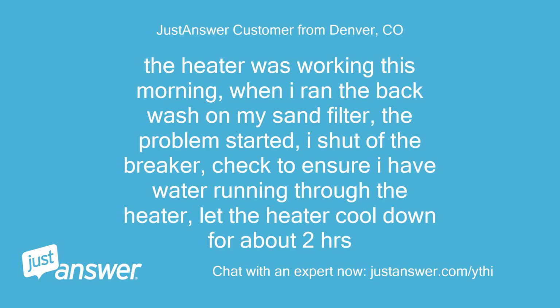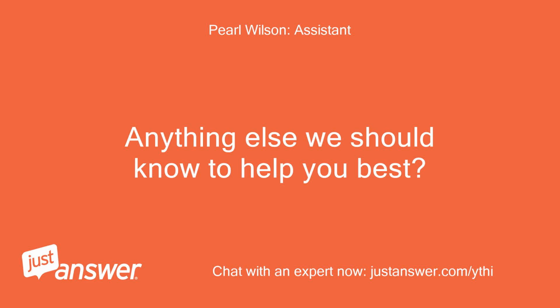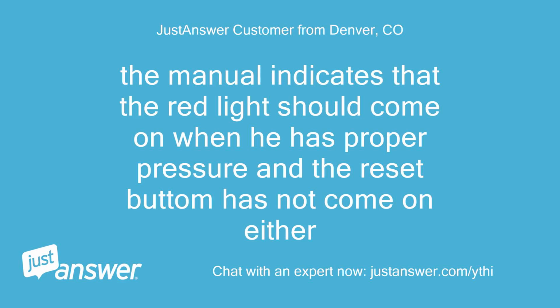The heater was working this morning. When I ran the backwash on my sand filter, the problem started. I shut off the breaker, checked to ensure I have water running through the heater, and let the heater cool down for about 2 hours. Anything else we should know to help you best? The manual indicates that the red light should come on when it has proper pressure, and the reset button has not come on either.